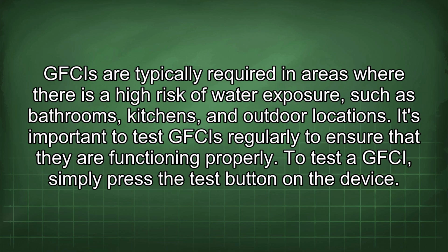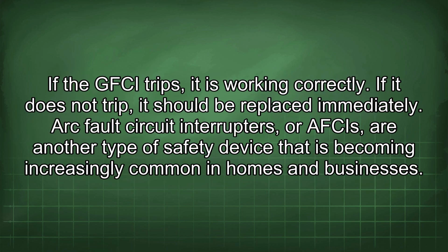GFCIs are typically required in areas where there is a high risk of water exposure, such as bathrooms, kitchens, and outdoor locations. It's important to test GFCIs regularly to ensure that they are functioning properly. To test a GFCI, simply press the test button on the device. If the GFCI trips, it is working correctly. If it does not trip, it should be replaced immediately.